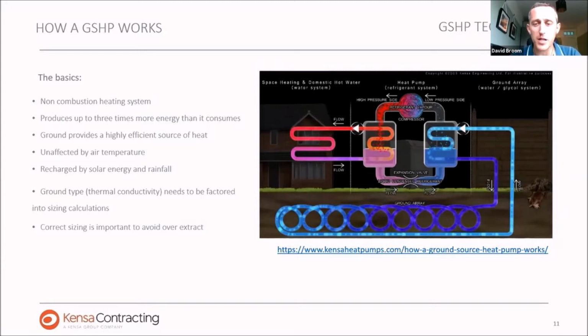With a ground source heat pump, in basic terms, what we're trying to do is gather a large volume of low-grade heat from an energy source, generally the ground. The ground loop, typically boreholes but can be other forms of energy, gathers that large volume of low-grade heat and takes it to the heat pump and into the compressor. The compressor, as part of the refrigerant circuit, compresses that energy, squeezes it, and upgrades it to higher pressure. As it does that, it increases the temperature and delivers useful hot water into the building.